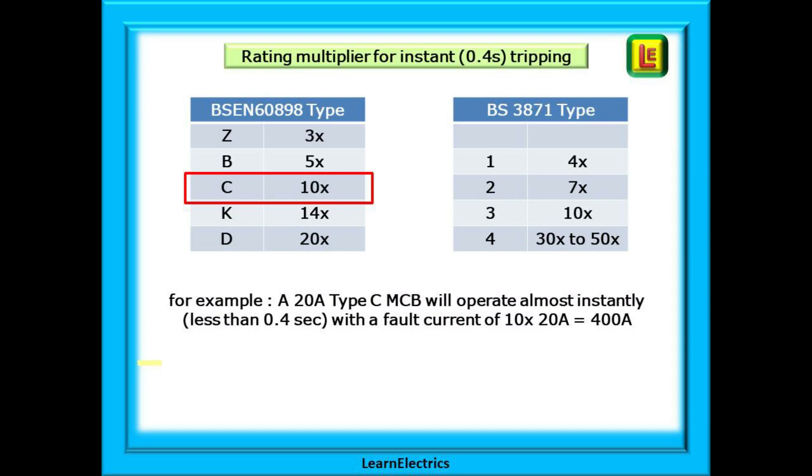The type number is actually a rating multiplier that tells us how quickly the device will do two things: how it will respond to real faults and how it will buffer itself against nuisance or startup tripping. Look at these two tables shown here. We've included the types Z and K but most often it will be types B, C and D that you come across. The B type will trip within 0.4 seconds if a short or fault current of 5 times its rating is detected. The type C will respond to the current of 10 times its rating and so on.